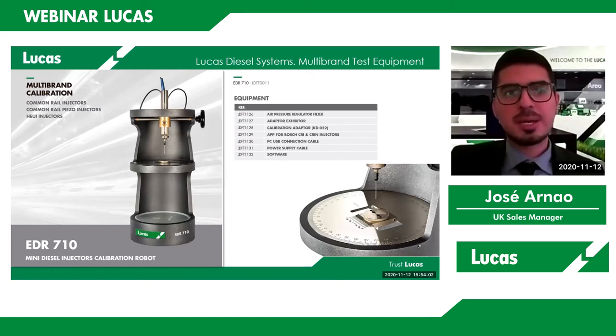This one is a semi-automatic calibration robot, because as you can see from the picture, there is a disc that the operator will need to calibrate manually when calibrating the shims. So this is the main difference, because all the other repeatability and tolerances guaranteed by the previous calibration system are guaranteed as well in this specific calibration robot.